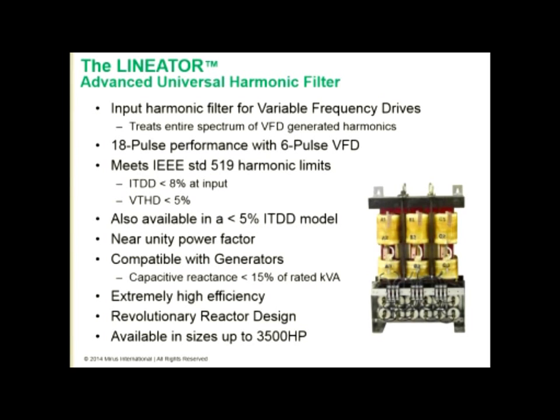By removing the harmonic content, we restore the power factor to near unity. We do this using a capacitor bank that is designed to keep the capacitive reactance less than 15% of the rated kVA of the filter. And this is how we can ensure compatibility with generators. And I'll talk a little bit more about that going forward.